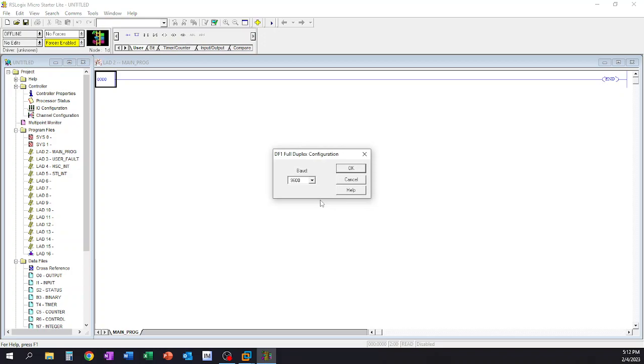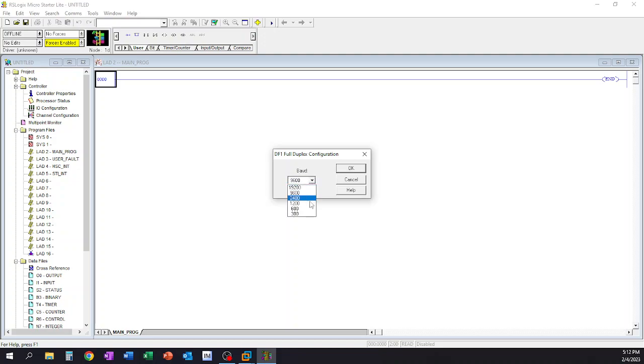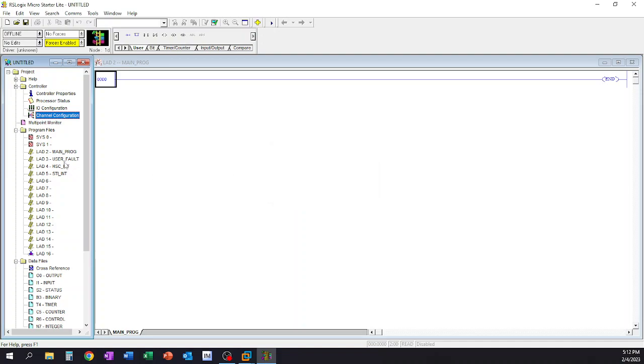Channel configuration. So because we only have the DF1 communications on a MicroLogix 1000, we don't have any communication setup. Now again, if we'd had like a 1747 on a SLC 5/05, we'd have ethernet, RS-232, and I think there's one other port that I'm kind of drawing a blank on at this moment. And we'd have the opportunity to go in and set like our IP address or some other information. But since we don't have that, our channel configuration is kind of left blank, except for what our baud rate speed would be. And we have the opportunity to change our baud rate depending on our particular criteria or need.